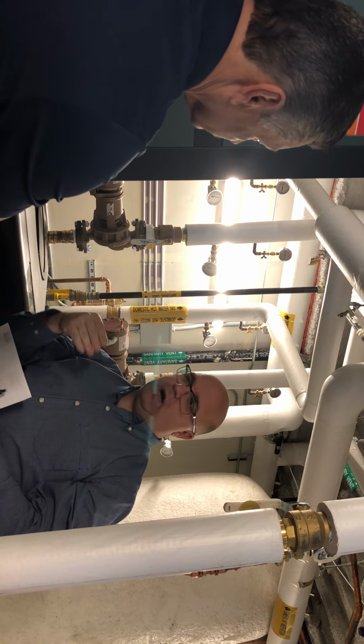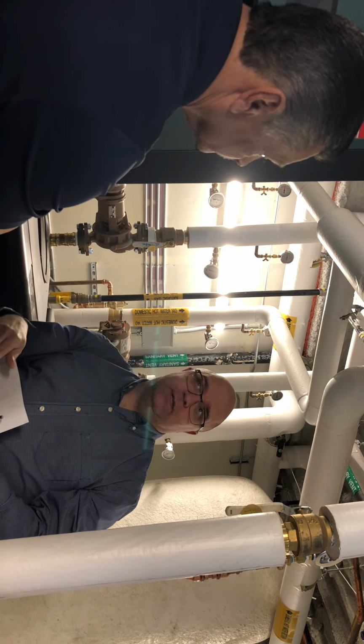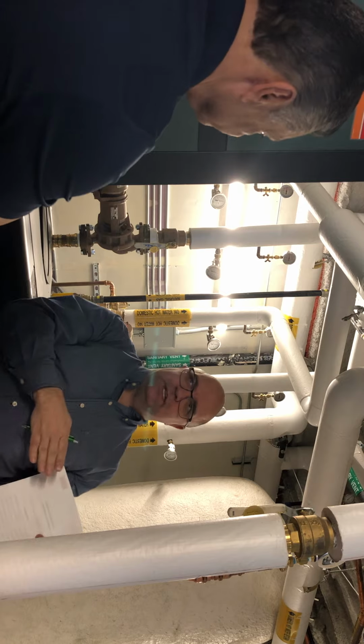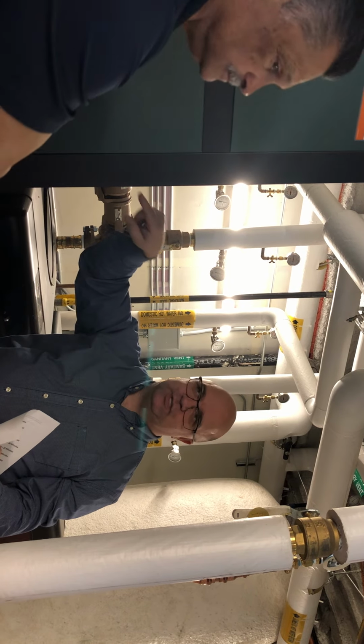With the exception of these valves will start to swing water and kind of short circuit these tanks if the water gets too cold. All right, 300 showers happen all at once, all of a sudden our domestic hot water temperature dives. I'm going to swing the water so that it shortcuts the tanks and gets us back into the boilers as soon as possible. And then it'll trigger its way back.